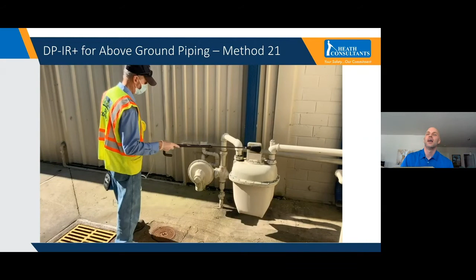Now, I guess one of the biggest upgrades for the DPIR Plus was the increased pump and the increased response time specifically for the instrument. I've got two videos here. If the sound isn't working, take a look at the numbers, because while you may not hear the actual alarms, you can still see the response time just by looking at the numbers. In this video, we've got an older DPIR on the left and the DPIR Plus on the right. Right now you can see the two probes at the top are on the same leak, so it's the same scenario here.